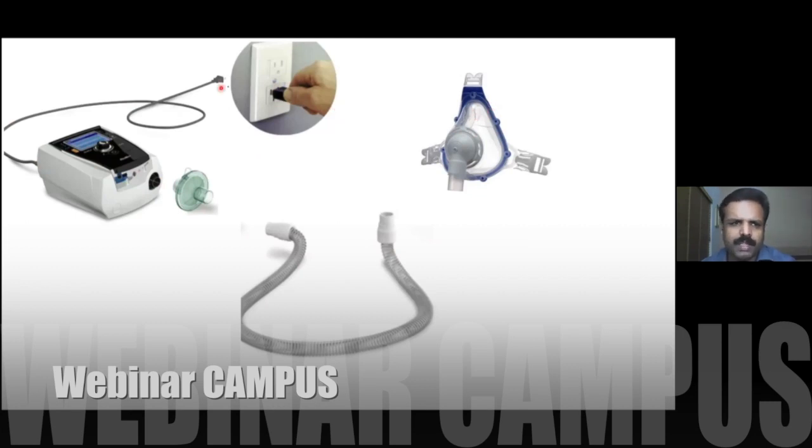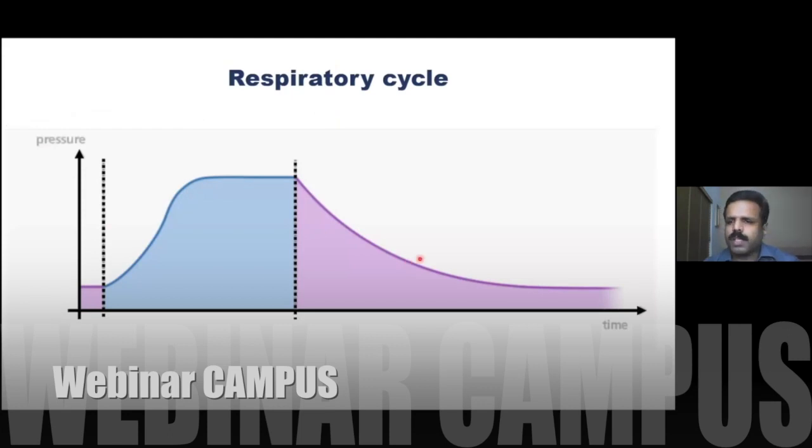After connecting, on the back side of the machine there will be a switch. You switch that on, then you will have to do the adjustment. And for the circuit, always use a sterile circuit. Don't reuse a circuit used for one patient on another patient. There are reusable circuits, but you will have to ETO sterilize those circuits. Clear?